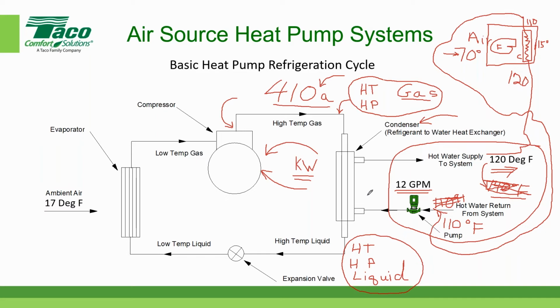Oh, there you go. So we've just described what happens to the refrigerant, and it gives up its heat to the water by condensing, and now we have a high temperature, high pressure liquid. Through the magic of the refrigeration process, it then passes through an expansion valve, which in its absolute simplest form is just an orifice. In the more sophisticated devices, it's a valve that opens and closes based on the discharge temperature of the evaporator. But we're just going to think of it as a very simple device like an orifice. When it passes through that orifice, it changes from a high temperature, high pressure liquid to a low temperature, low pressure liquid. And then it enters the evaporator.